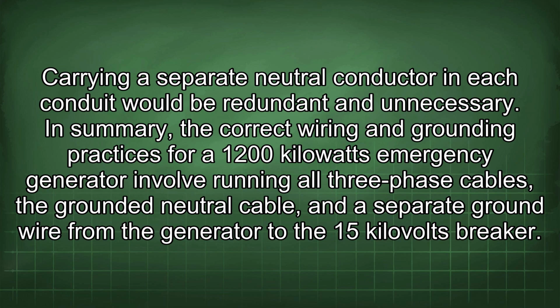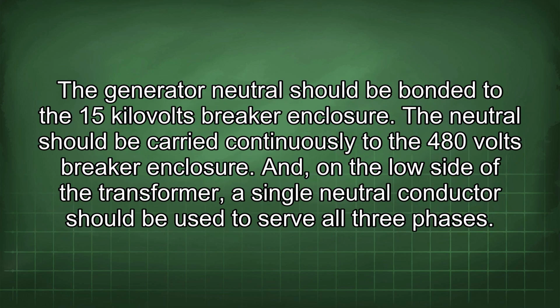In summary, the correct wiring and grounding practices for a 1200 kilowatts emergency generator involve running all 3-phase cables, the grounded neutral cable, and a separate ground wire from the generator to the 15 kilovolts breaker. The generator neutral should be bonded to the 15 kilovolts breaker enclosure. The neutral should be carried continuously to the 480 volts breaker enclosure. And, on the low side of the transformer, a single neutral conductor should be used to serve all 3 phases.